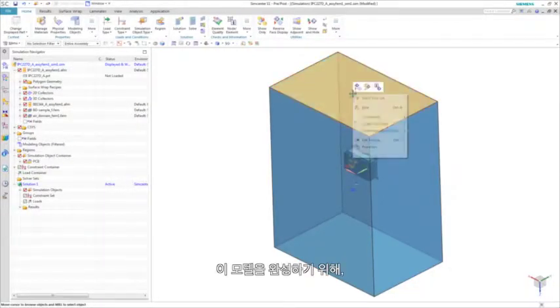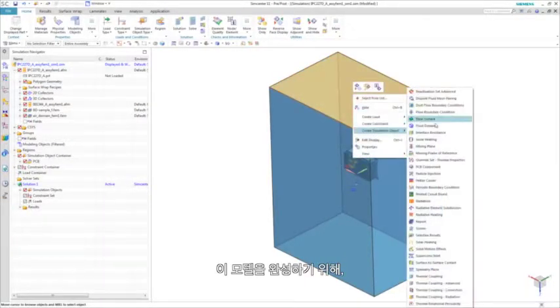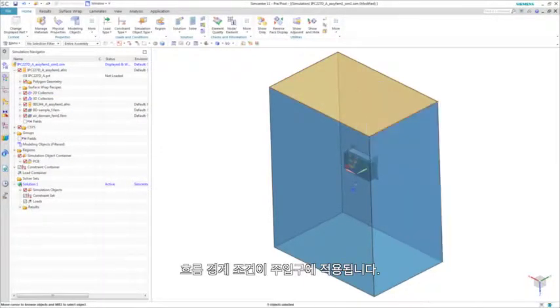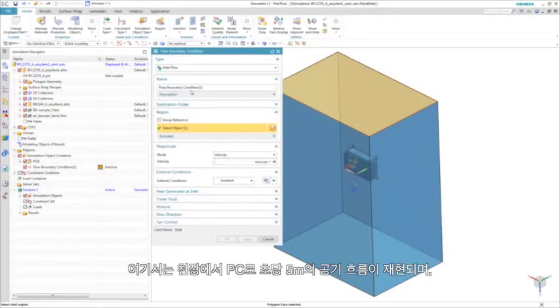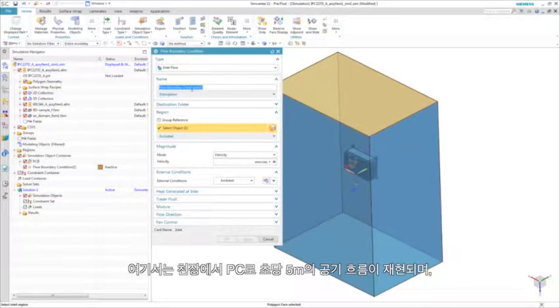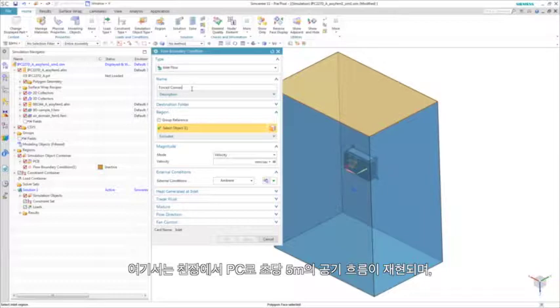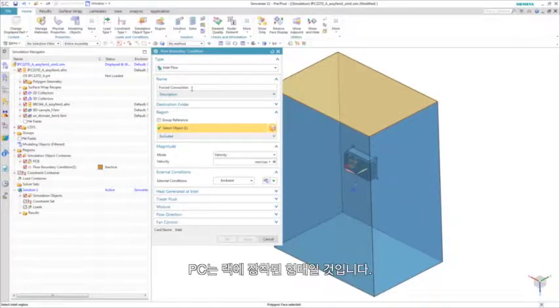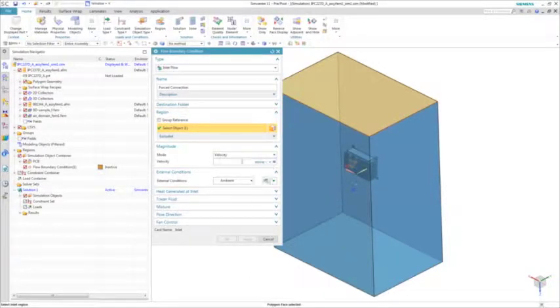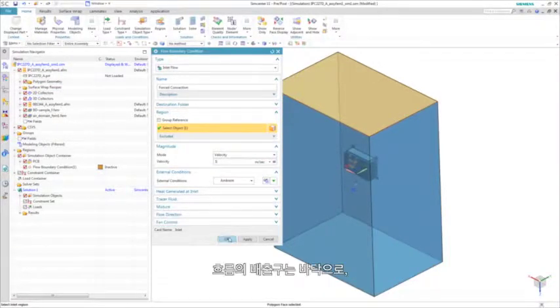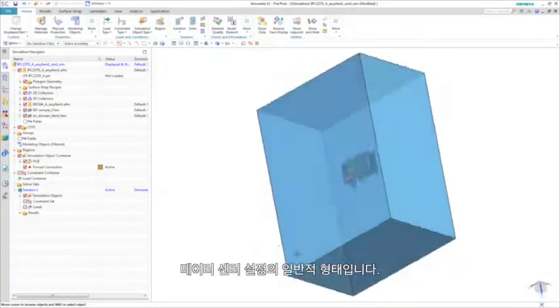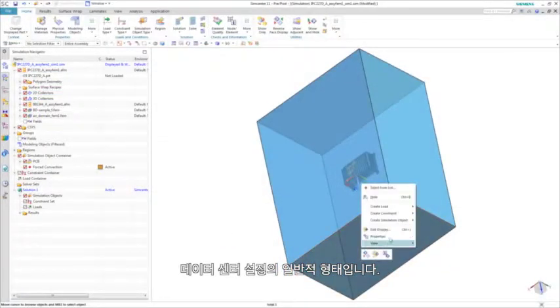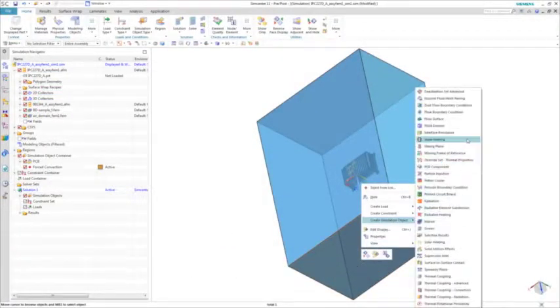To complete this model, flow boundary conditions are applied at an inlet to represent forced air flow of 5 meters per second from the ceiling onto the PC, which would be rack mounted. The flow outlet would be on the floor, which is typical of a data center setup.